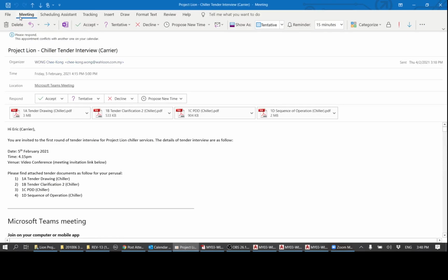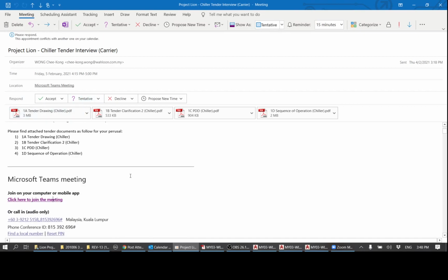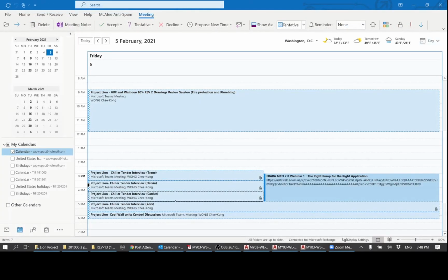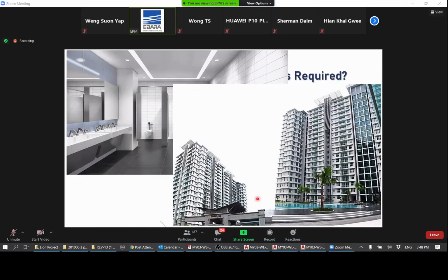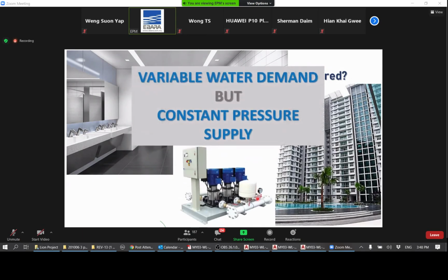Or perhaps even a multi-storey condominium, which is very common in our city, with many water demand points for each household unit. Depending on the time of the day, the demand for water will vary according to the number of users or occupancy of the building. So having a pump system with a multiple pump arrangement to achieve this variable demand condition ensures that each pump runs efficiently while delivering constant pressure supply at all times. That's what a whole booster set package is designed for.